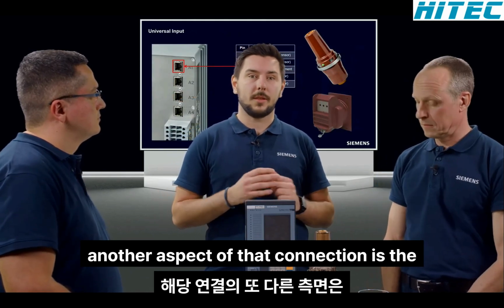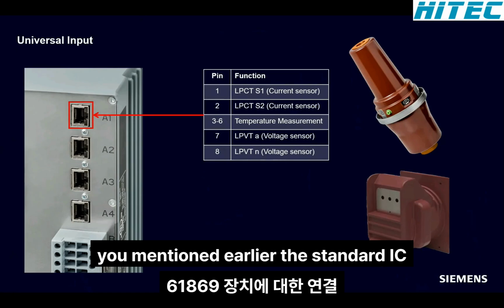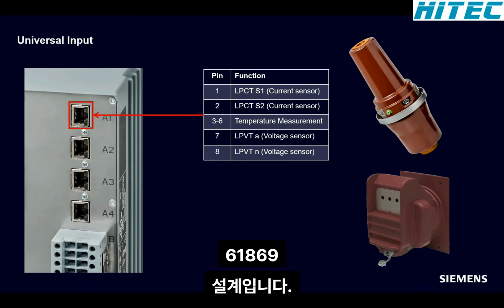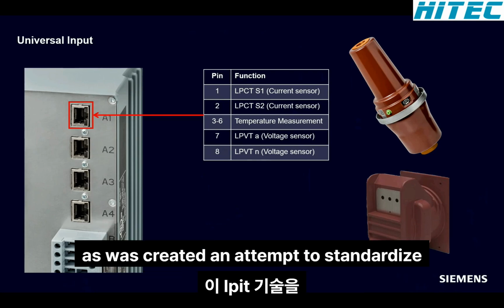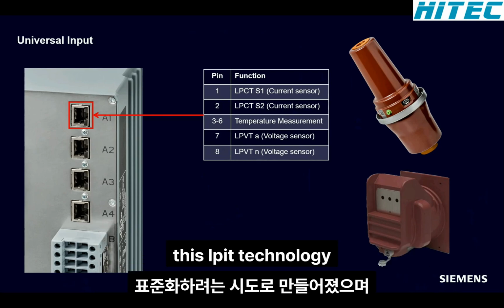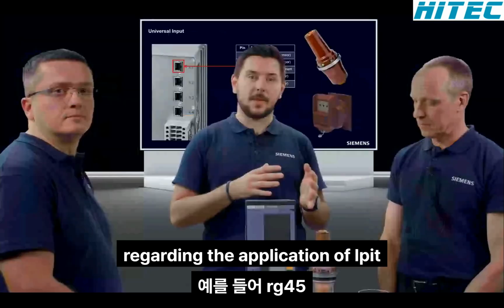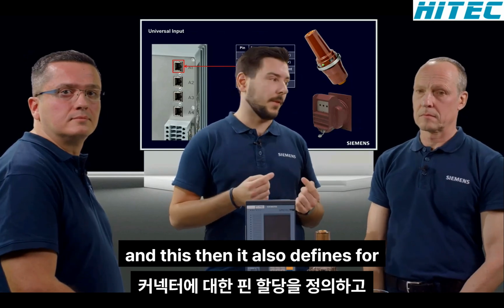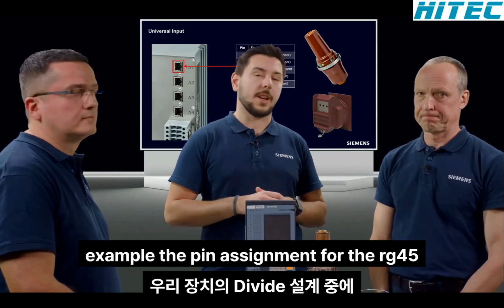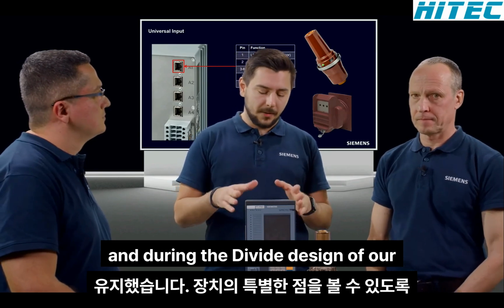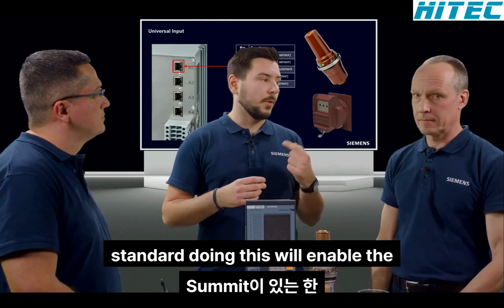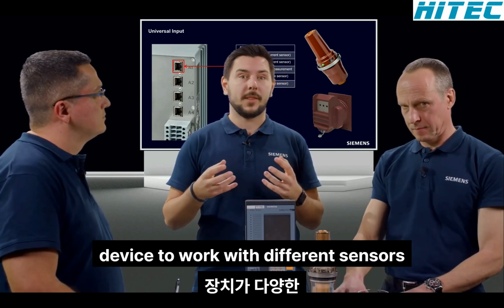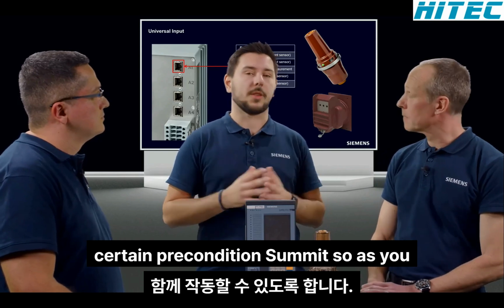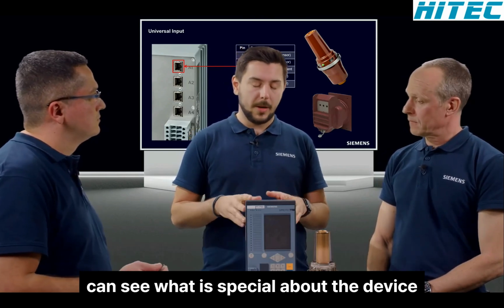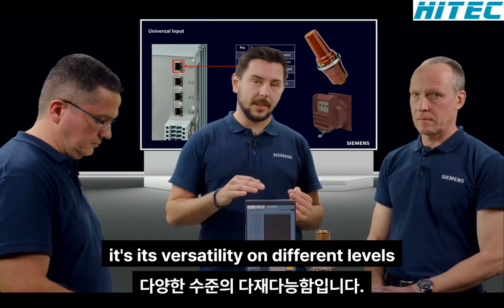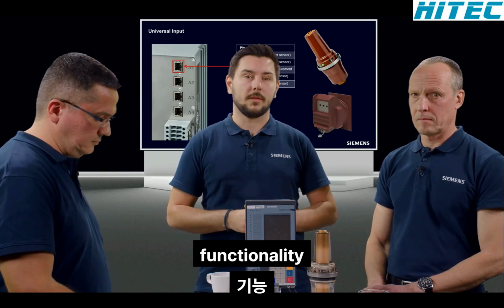Another aspect of the connection is the design of the connection to the device. You mentioned earlier the standard IEC 61869. This was created in an attempt to standardize this LPIT technology regarding the application of LPIT. And this standard also defines, for example, the pin assignment for the RJ45 connectors. And during the design of our device, we kept it compliant to the standard. Doing this will enable the device to work with different sensors from various manufacturers as long as certain preconditions are met. So as you can see, what is special about the device is its versatility on different levels, the measuring inputs and the protection functionality.